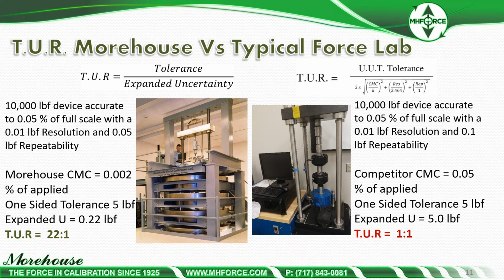This is something on how that looks. So I have a 10,000 pound load cell with an accuracy of 0.05% of full scale with a 0.01 pound resolution. If I run these through the formulas, 2 things are going to change here. One, basically the repeatability in a machine that's not as plumb, level, square and rigid as the other machine, maybe the alignment's not as good, of my unit under test is going to change, as well as my CMC uncertainty parameter. Here we're using a dead weight machine, 20 parts per million, and we're comparing it with a secondary standard used by many of the labs down in the pyramid, as many of our competitors use, of 0.05%. Big difference, you have a TUR of 22 to 1 versus 1 to 1.